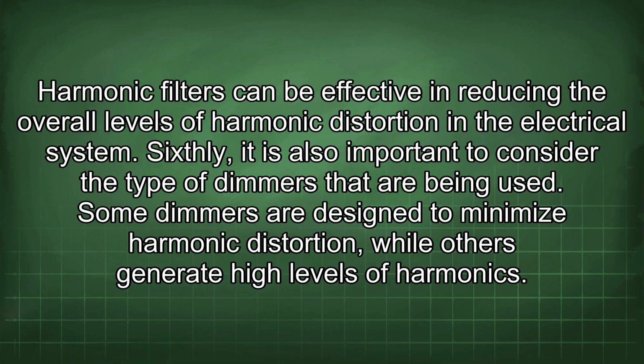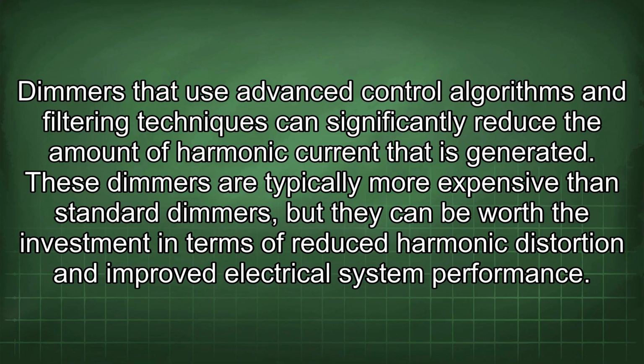Sixthly, it is also important to consider the type of dimmers that are being used. Some dimmers are designed to minimize harmonic distortion, while others generate high levels of harmonics. Dimmers that use advanced control algorithms and filtering techniques can significantly reduce the amount of harmonic current that is generated. These dimmers are typically more expensive than standard dimmers, but they can be worth the investment in terms of reduced harmonic distortion and improved electrical system performance.